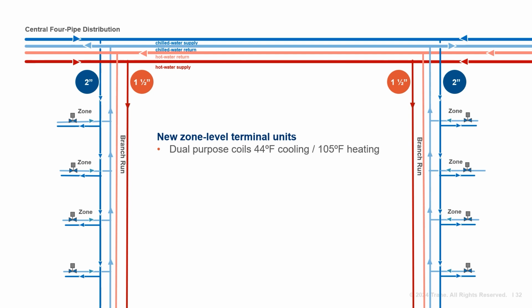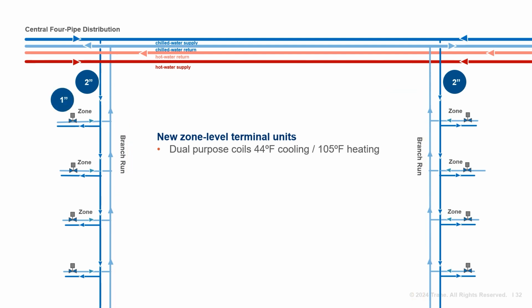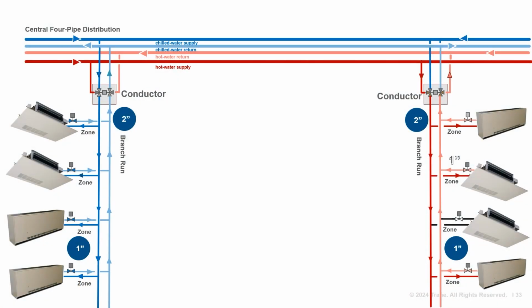This 2-inch branch chilled water piping is already correctly sized for heating also. So this branch hot water piping is no longer needed. It can be disconnected, drained, capped, and left in place to prevent disruption to the finished space. Or it can be reused if there is heating-only equipment installed. With the new terminal units, switchover occurs at the branch connection for each thermal area.